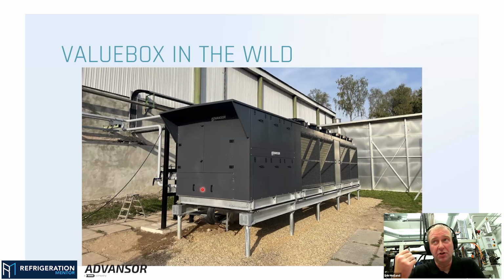Just on a normal supermarket system, we charge directly into the receiver, because then we have the whole refrigeration system to help us keep the pressure low if it's getting too high. That's super easy. On this system here, we found that it's a good idea to start with the receiver, fill up the receiver, fill up the liquid lines. The volumes are not that big because the machine room is all here. All the refrigeration system is basically only in here and in the feed lines out here, so it's a very small pipe volume and quite easy to fill up.